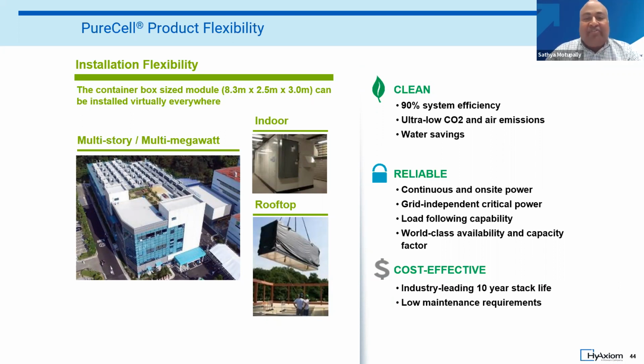These fuel cells are very simple machines, used for continuous on-site power, and they can run independent of the grid. Your building runs on the fuel cell in parallel with the grid, and the grid becomes your backup. The beauty of lower to medium temperature fuel cells is that they can load follow—if you don't want to use the entire load all the time, they can manage the cycle like your building or factory cycles.